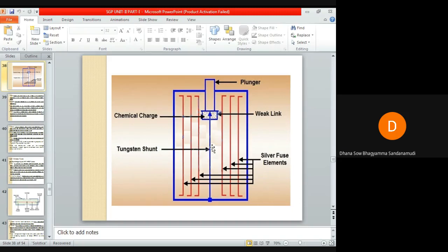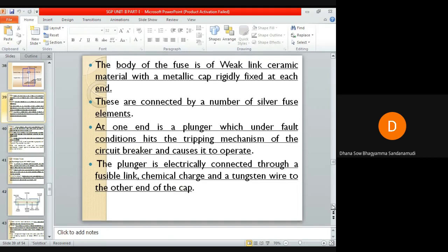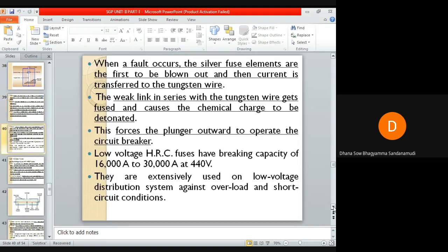This is a low voltage HRC fuse having a breaking capacity of 16,000 amperes to 30,000 amperes at 440 volts. They are extensively used on low voltage distribution systems against overload and short circuit conditions. So this is about low voltage fuses.